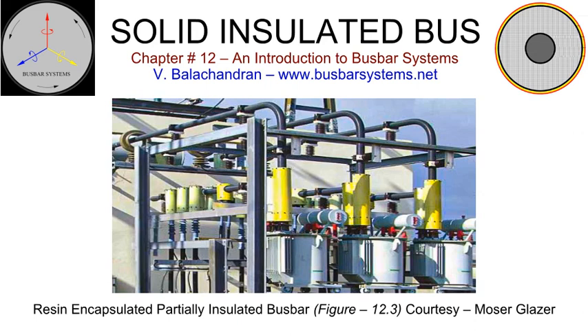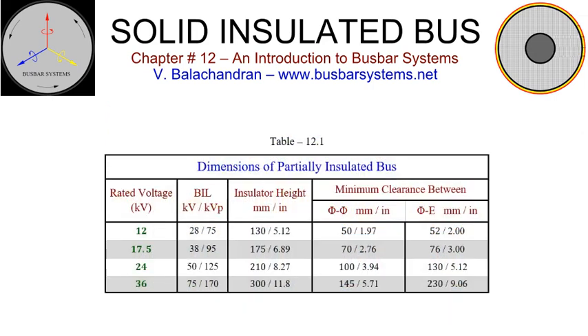Since the clearances to other phase conductors and earth are significantly reduced due to the conductor insulation, the entire assembly of a three-phase connection becomes compact. Table 12.1 details typical phase spacing and height of the insulators for different voltages. Rated voltage, basic insulation level, minimum height of the insulators, phase-to-phase and phase-to-earth clearances, for rated voltages varying from 12 kV to 36 kV.